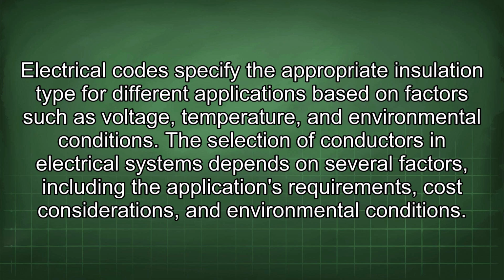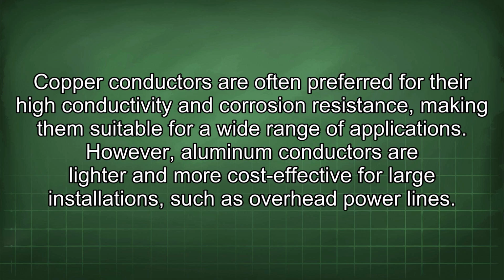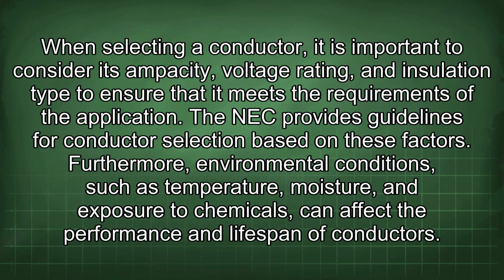The selection of conductors in electrical systems depends on several factors, including the application's requirements, cost considerations, and environmental conditions. Copper conductors are often preferred for their high conductivity and corrosion resistance, making them suitable for a wide range of applications. However, aluminum conductors are lighter and more cost-effective for large installations, such as overhead power lines. When selecting a conductor, it is important to consider its ampacity, voltage rating, and insulation type to ensure that it meets the requirements of the application. The NEC provides guidelines for conductor selection based on these factors.